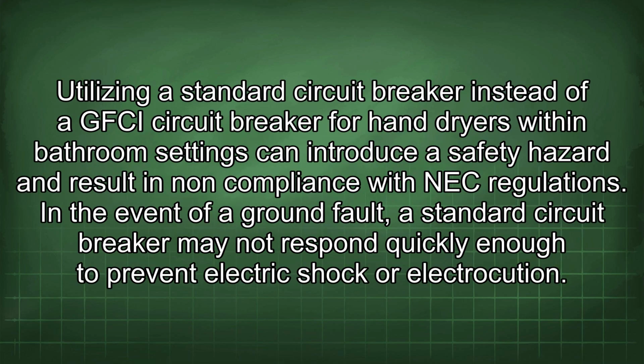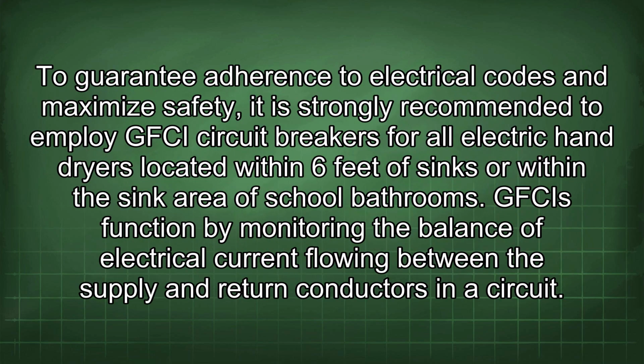Utilizing a standard circuit breaker instead of a GFCI circuit breaker for hand dryers within bathroom settings can introduce a safety hazard and result in non-compliance with NEC regulations. In the event of a ground fault, a standard circuit breaker may not respond quickly enough to prevent electric shock or electrocution. To guarantee adherence to electrical codes and maximize safety, it is strongly recommended to employ GFCI circuit breakers for all electric hand dryers located within 6 feet of sinks or within the sink area of school bathrooms.